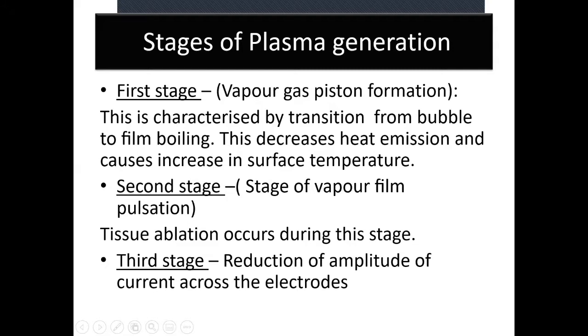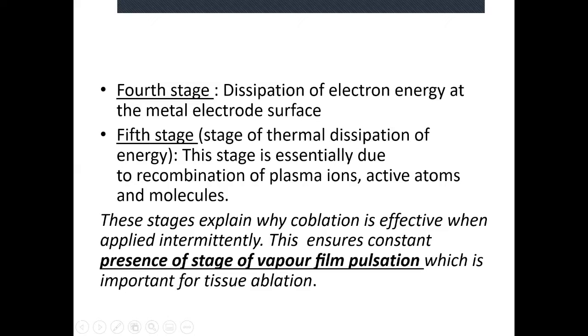The first phase is called the vapor gas piston formation stage, characterized by a transition from bubble to film boiling — this decreases heat emission. The second stage is vapor film pulsation — tissue ablation actually happens in this stage. The third stage involves reduction of amplitude of current across the electrodes, controlled by the console. The fourth and fifth stages are respectively dissipation of electron energy and thermal dissipation.